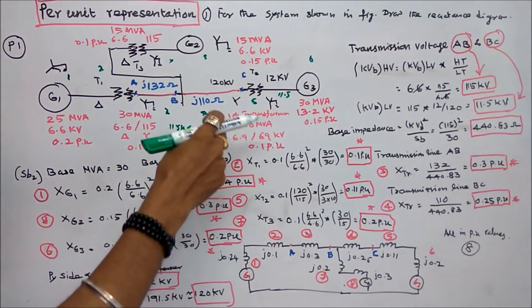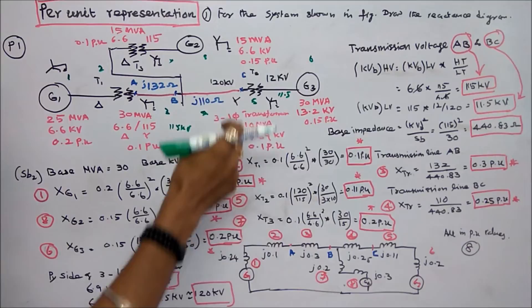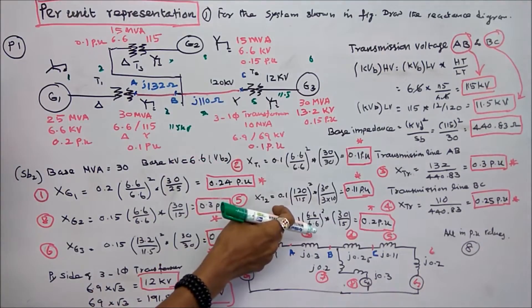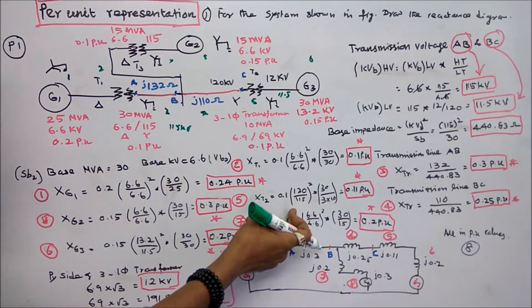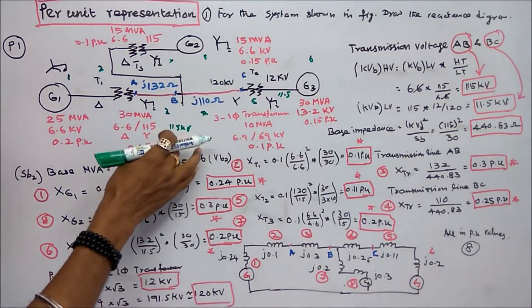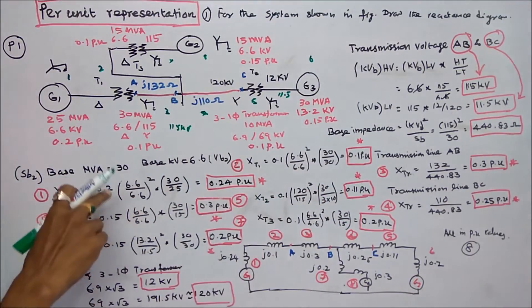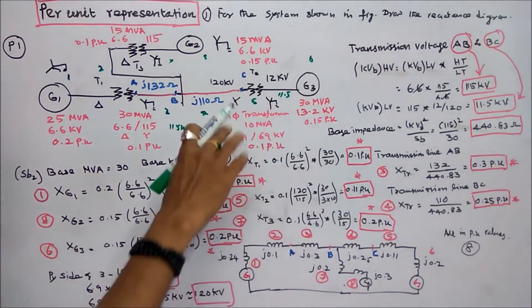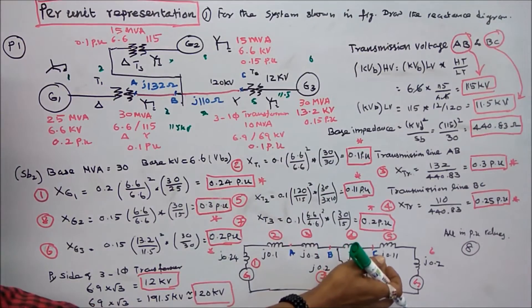The fifth component is the bank of three single-phase transformers: 3 × 10 = 30 MVA. The per unit reactance = 0.1 × (120/115)² × (30/30) = 0.11 per unit.